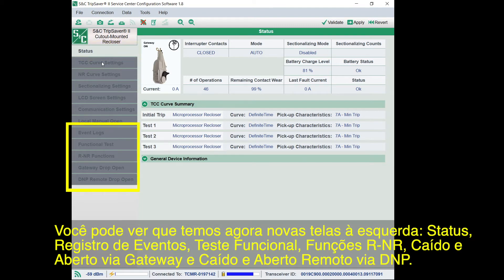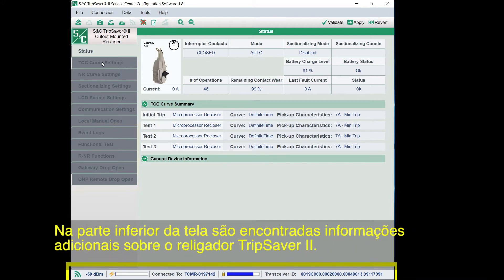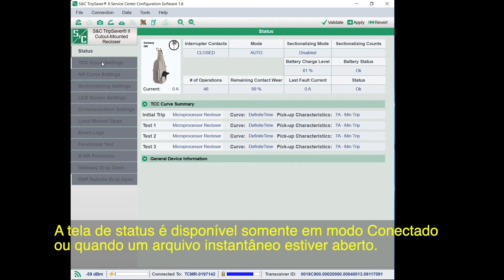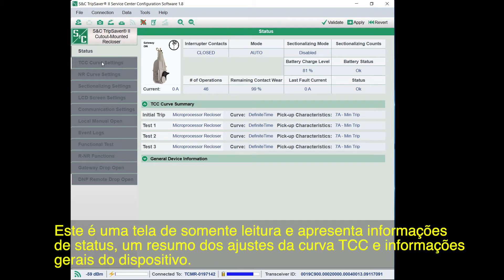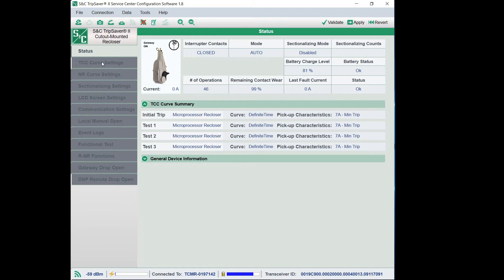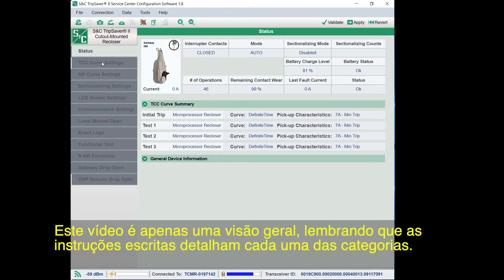The new screens in Connected mode include Status, Event Logs, Functional Test, R-NR Functions, Gateway Drop Open, and DNP Remote Drop Open. At the bottom of the screen, you'll find additional information about your TripSaver 2 recloser. The Status screen is only available in Connected mode or when a snapshot file is open. It's a view-only screen presenting status information, a summary of TCC curve settings, and general device information — a good place for a quick look at settings. This video is more of a general overview, but the written instructions go through each and every category on the page.